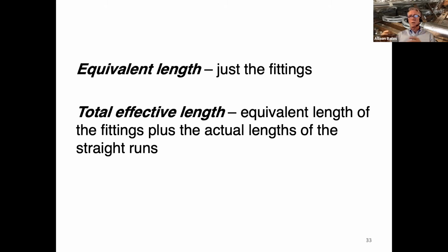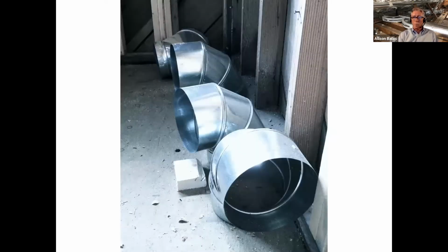So if you have a fitting and it says the equivalent length is 30 feet, that means the pressure drop of the air going through that fitting is equivalent to the pressure drop in 30 feet of straight duct. So when you add up all of the equivalent lengths of the fittings to the lengths of the straight ducts, then you get the total effective length. And that number gets calculated into something called the friction rate. We're not going to go into those details, but you've got to get the available static pressure and the total effective length, then you calculate the friction rate, and that tells you whether you have a good duct system or not. So fittings are where the action is at.